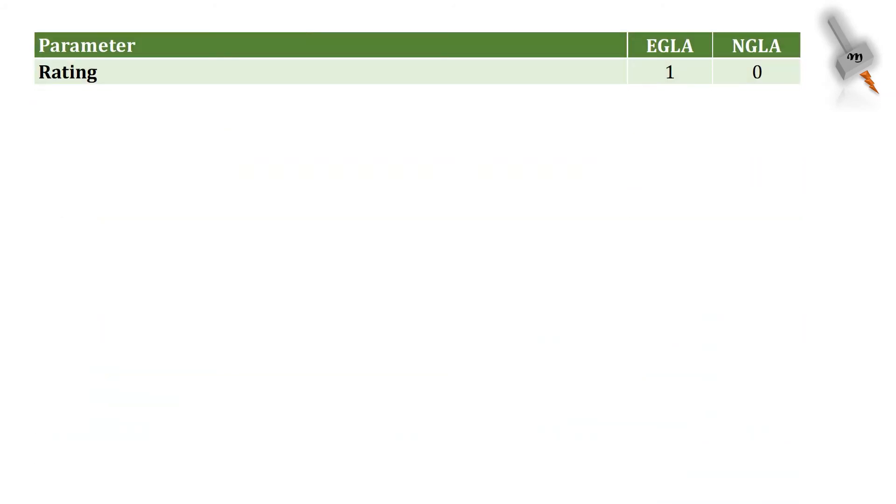So, let's summarize our learnings. In terms of rating, EGLA has better advantage since it can be rated lower still rendering same performance as NGLA. In terms of cost, the overall cost of EGLA is lower than NGLA due to low energy requirement and simple design in terms of hardware. Hence, EGLA has the advantage. In terms of weight of the product, since EGLA has less material content, the weight is also lower than the NGLA.